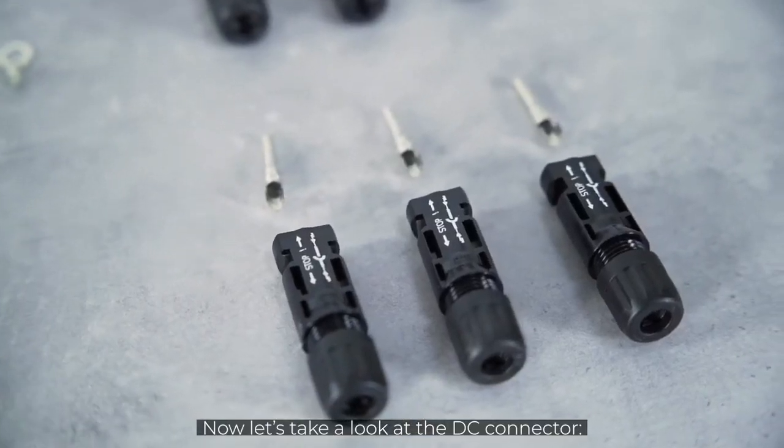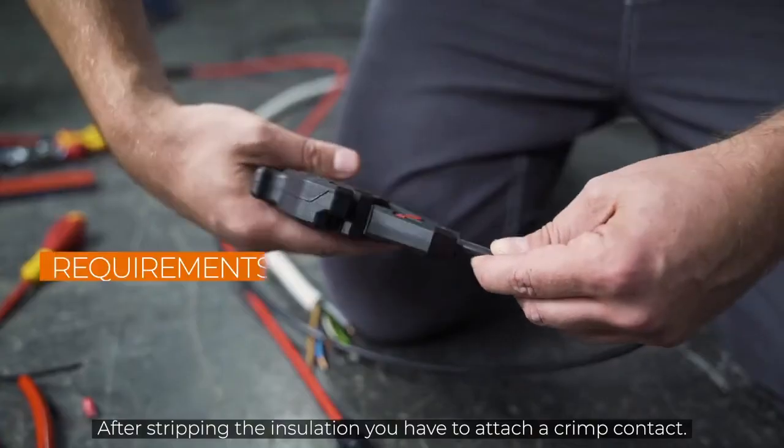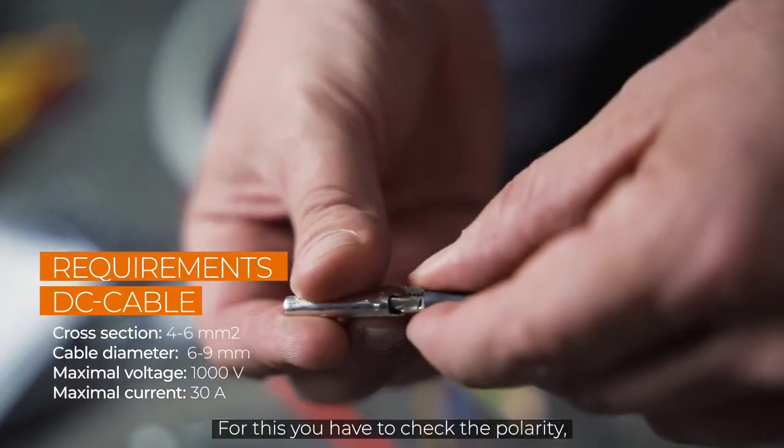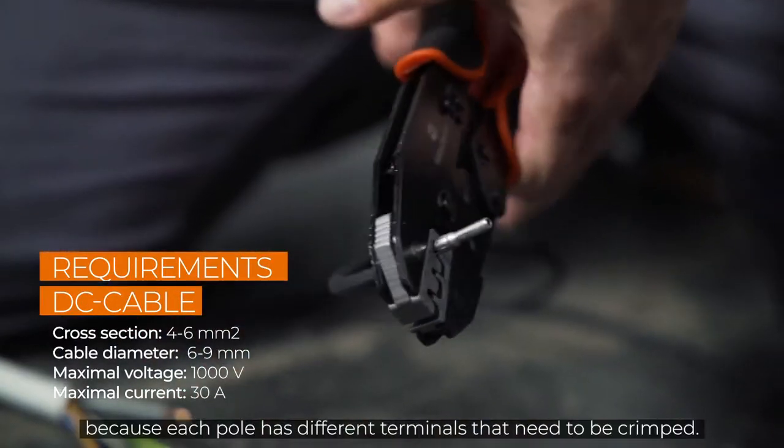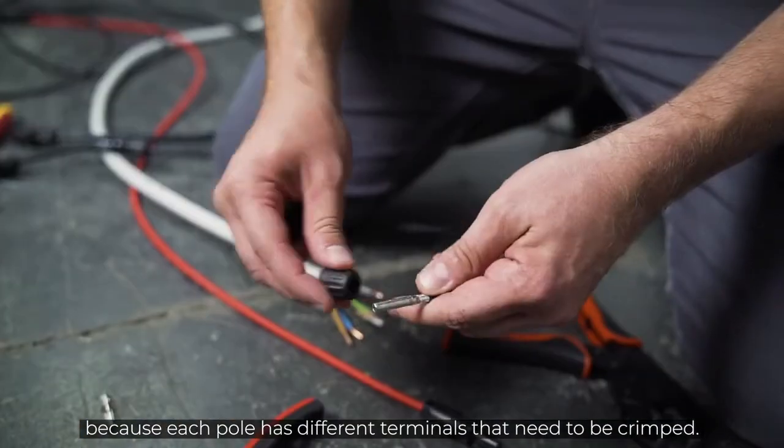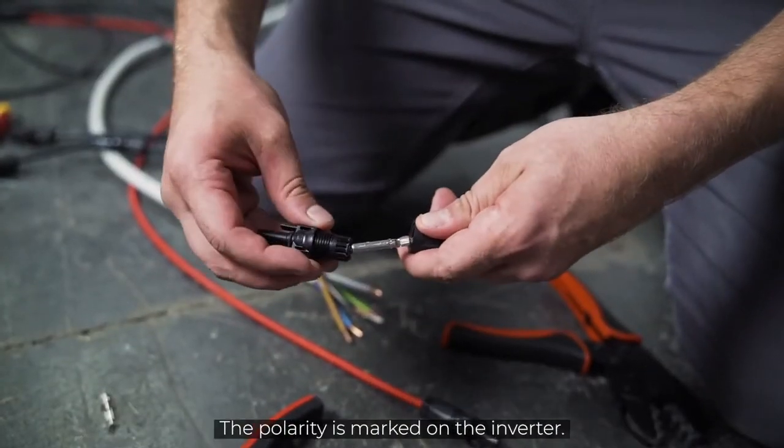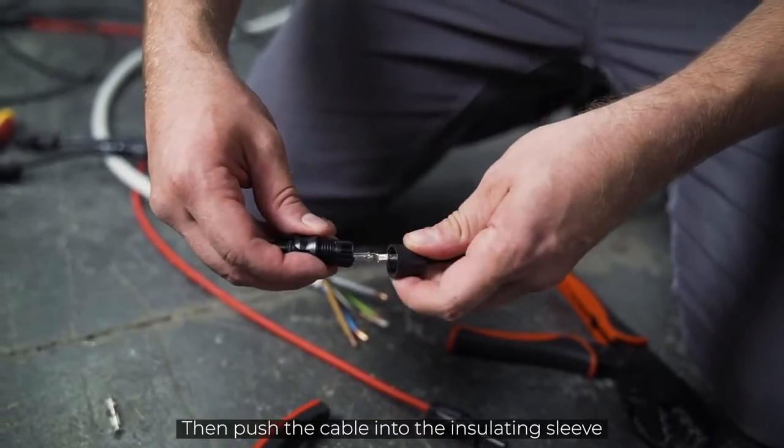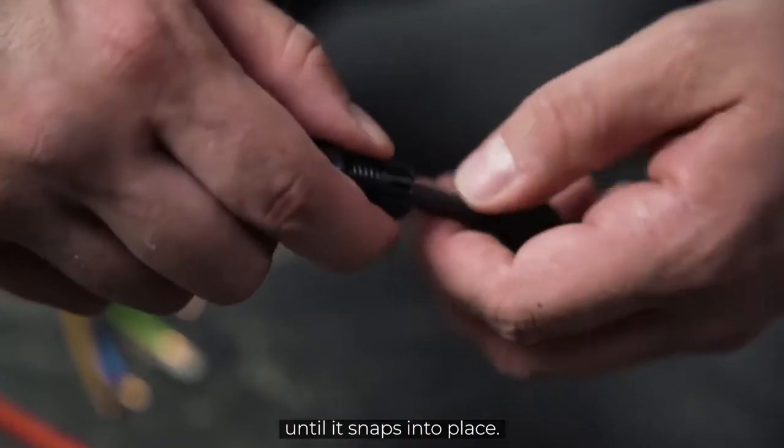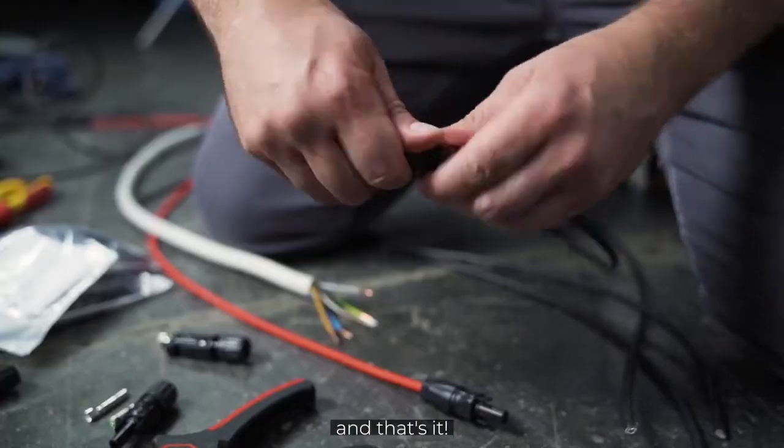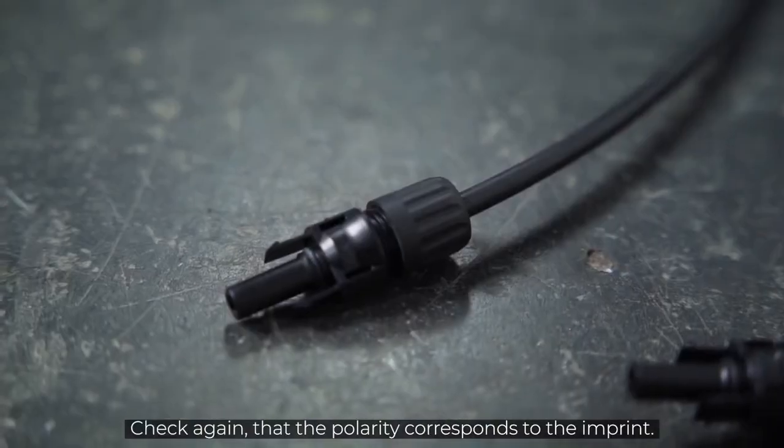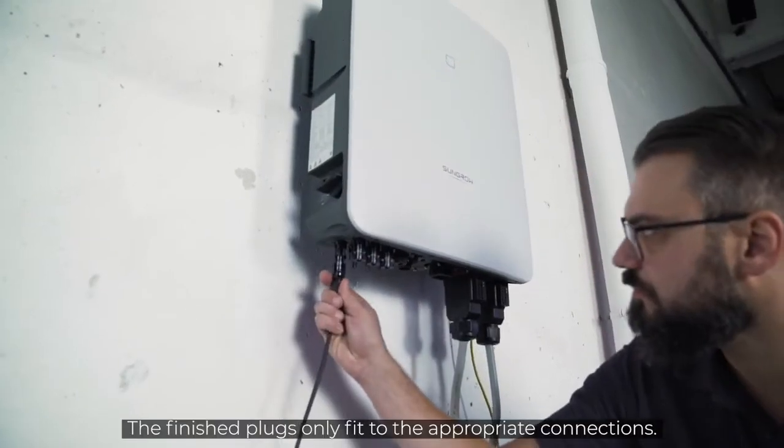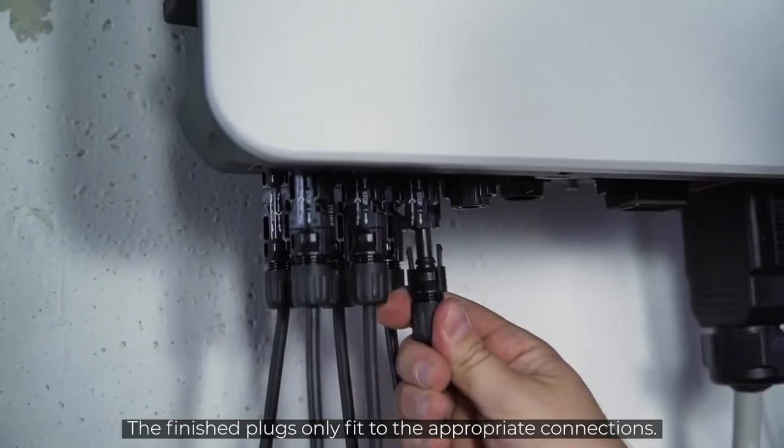Now let's take a look at the DC connector. After stripping the insulation, you have to attach a crimp contact. For this, you have to check the polarity because each pole has different terminals that need to be crimped. The polarity is marked on the connector. Then push the cable into the insulating sleeve until it snaps into place. Screw it and that's it. Check again that the polarity corresponds to the imprint. The finished plugs only fit to the appropriate connections.